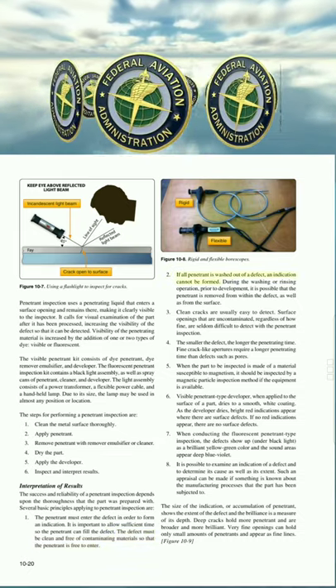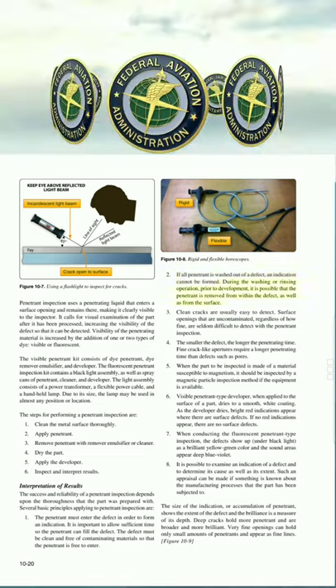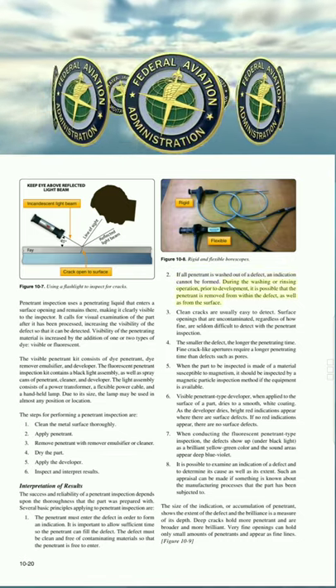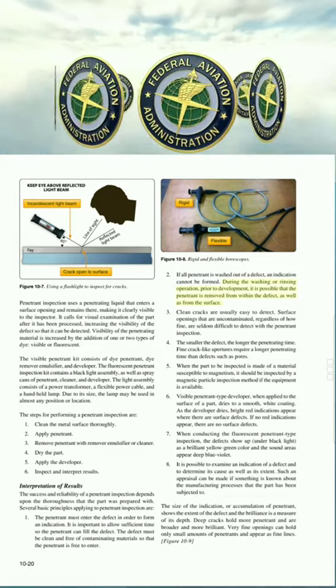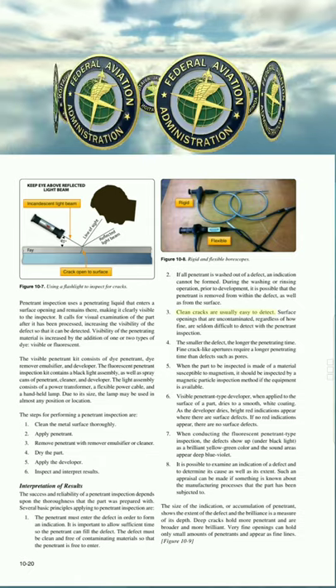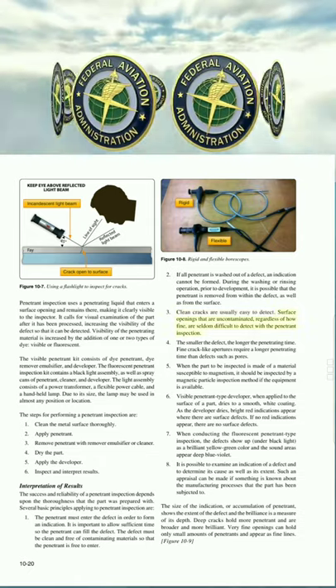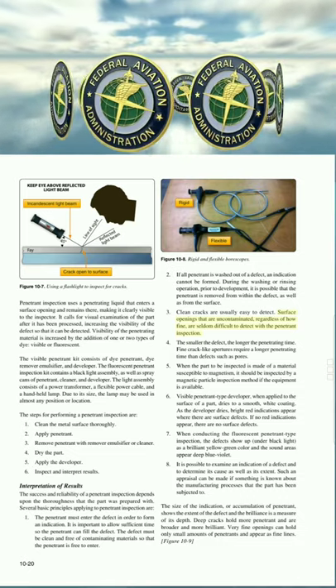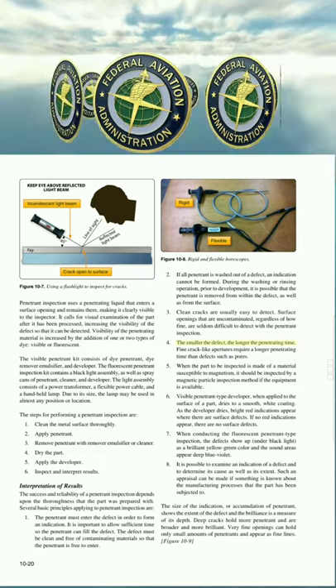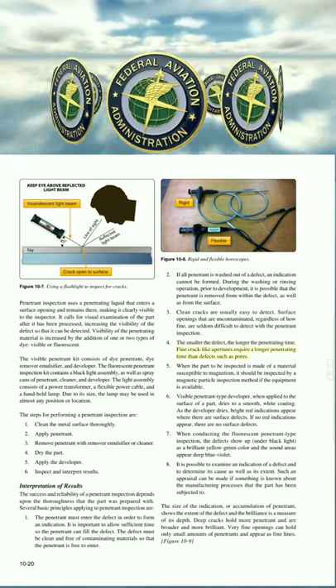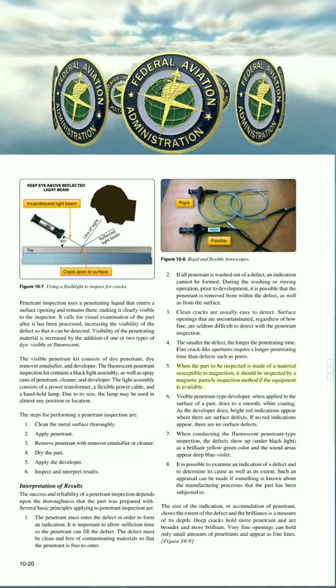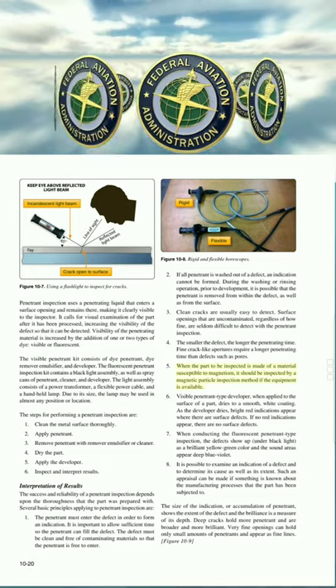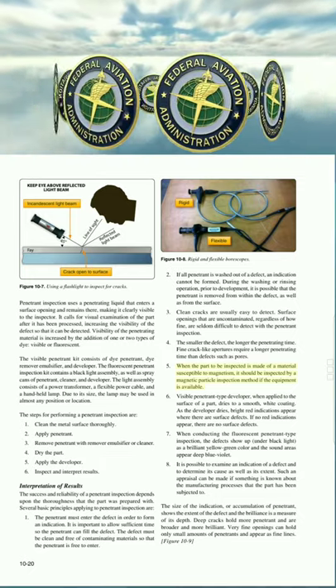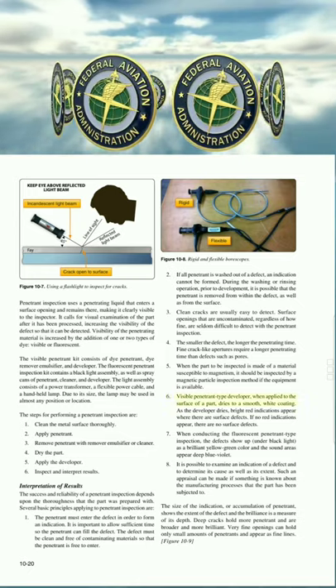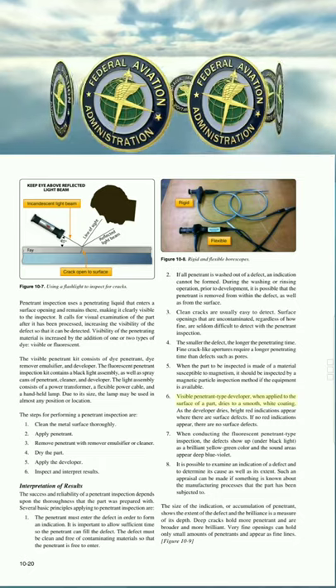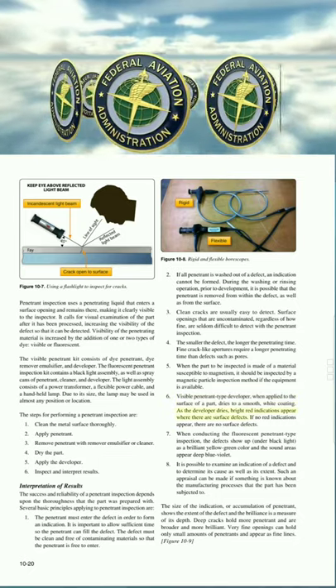2. If all penetrant is washed out of a defect, an indication cannot be formed. During the washing or rinsing operation, prior to development, it is possible that the penetrant is removed from within the defect, as well as from the surface. 3. Clean cracks are usually easy to detect. Surface openings that are uncontaminated, regardless of how fine, are seldom difficult to detect with the penetrant inspection. 4. The smaller the defect, the longer the penetrating time. Fine crack-like apertures require a longer penetrating time than defects such as pores. 5. When the part to be inspected is made of a material susceptible to magnetism, it should be inspected by a magnetic particle inspection method, if the equipment is available. 6. Visible penetrant type developer, when applied to the surface of a part, dries to a smooth, white coating. As the developer dries, bright red indications appear where there are surface defects.